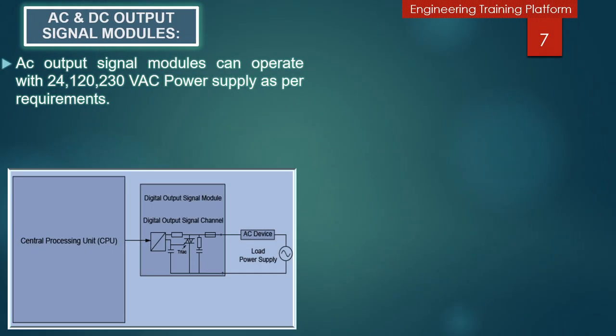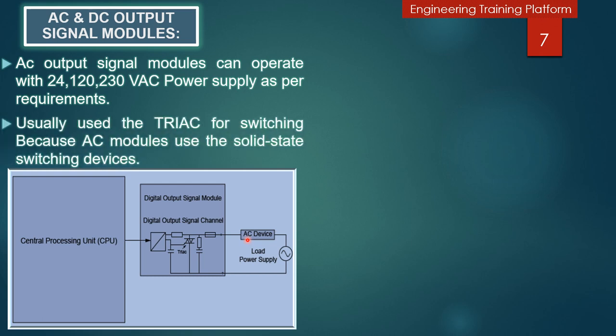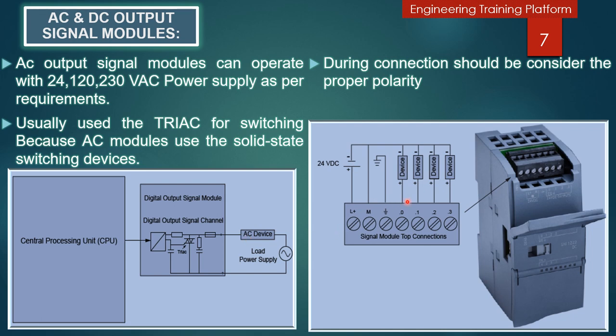The AC output signal modules typically operate with a load power supply of 24 volt, 120 to 230 volt AC, or may be capable of operating with either source. These modules use solid-state switching devices — usually a triac — to control each output. This type of output works reliably for many AC output devices; however, triacs allow a small leakage current to flow when the output is off, which is not suitable for some AC devices. You can also see in the picture eight output signal modules — four on top and four on the bottom — shown with source-type connections.